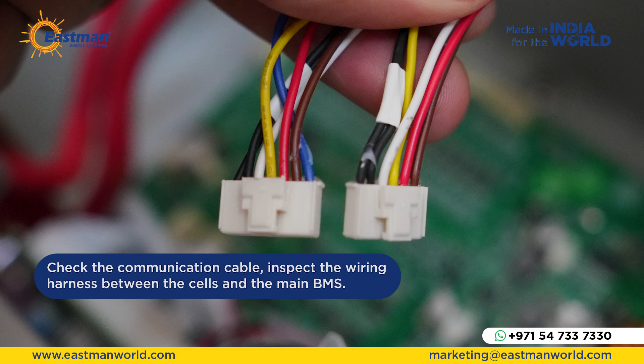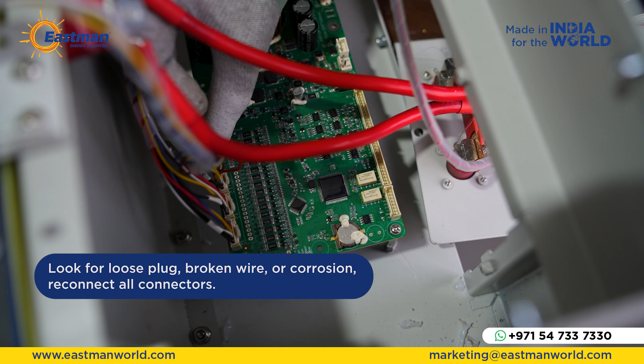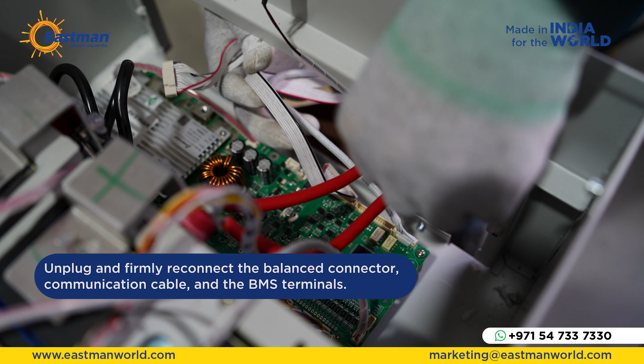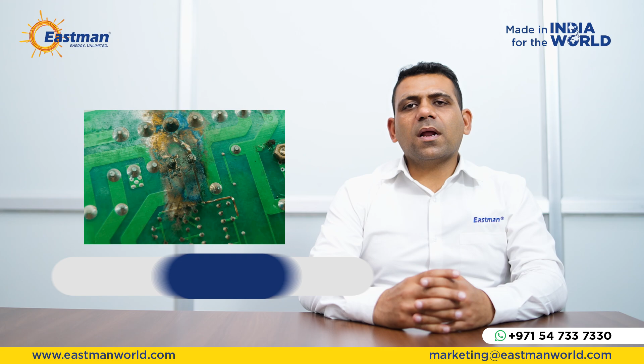Check the communication cable. Inspect the wiring harness between the cells and the main BMS. Look for loose plug, broken wire or corrosion. Reconnect all connectors. Unplug and firmly reconnect the balance connector, communication cable and the BMS terminals. Even a loose connection can cause this fault. Inspect the BMS board. Look for burn marks, corrosion, cracked components or loose solder joints. If anything is found loose, it needs to be fixed correctly.